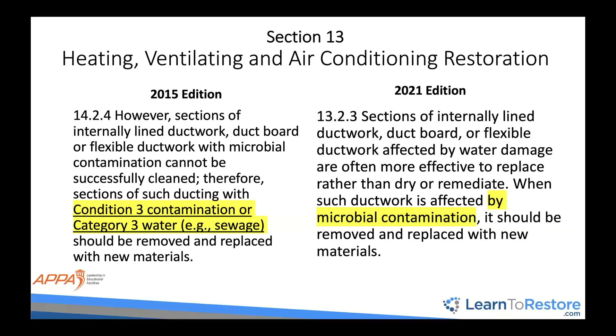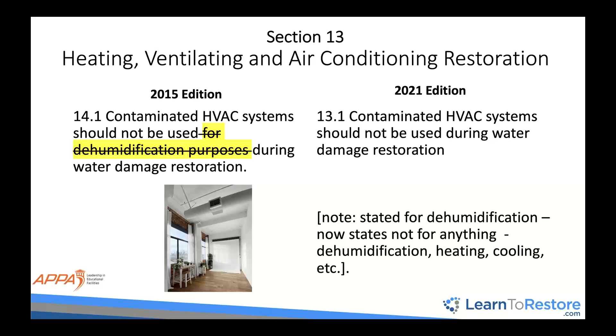It said previously that contaminated HVAC systems should not be used for dehumidification. All they did is take that out and say they shouldn't be used for anything. The HVAC, the lungs of the structure, is designed to uniformly move air, including whatever contamination is in that air. If it's contaminated, don't turn it on. Don't try and use it for dehumidification, for cooling, for heating, for whatever, until it's been cleaned and decontaminated, or you're going to cross-contaminate.